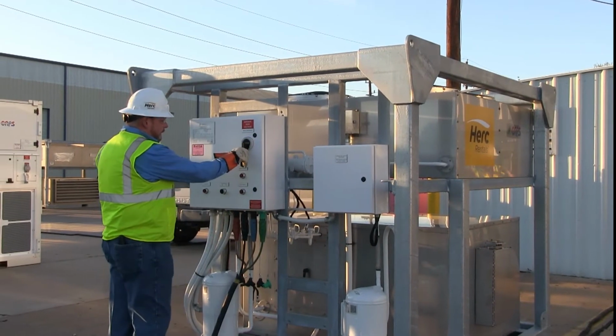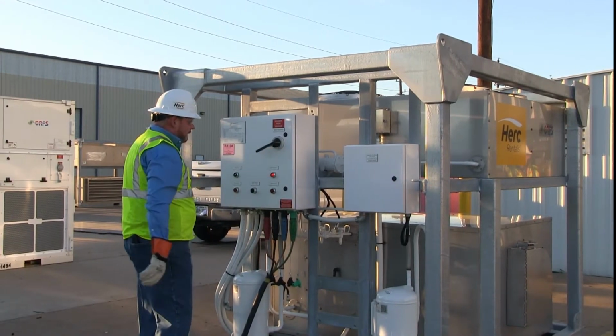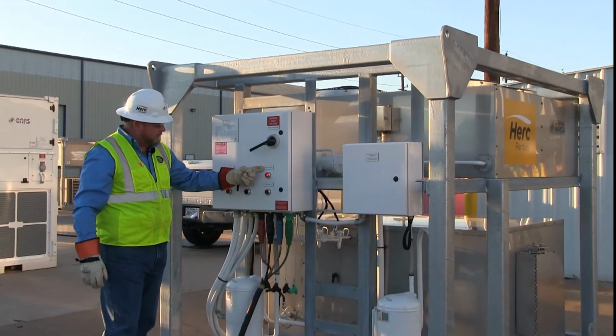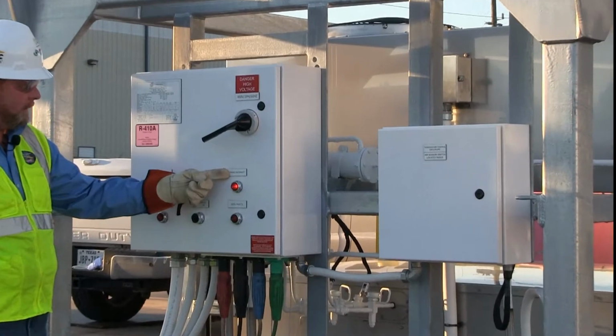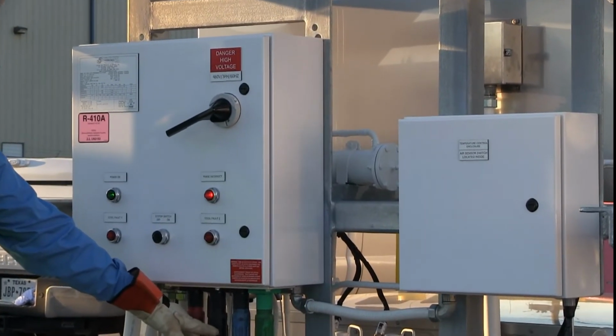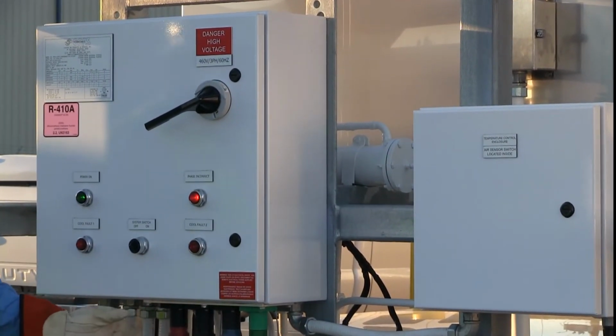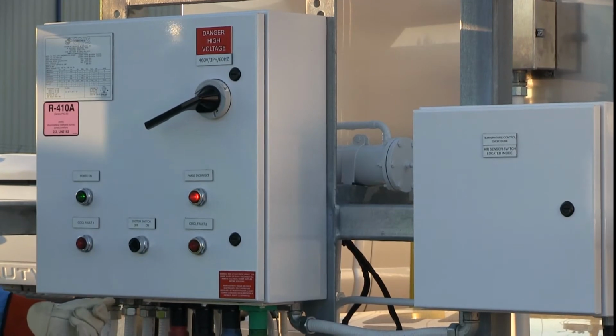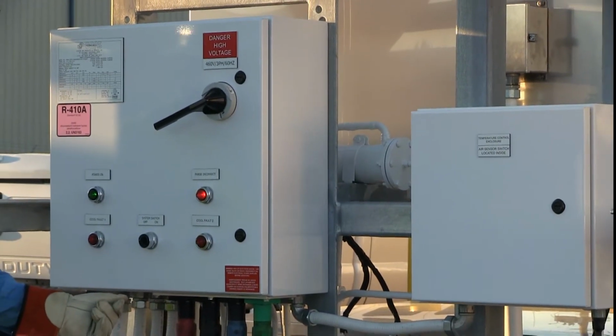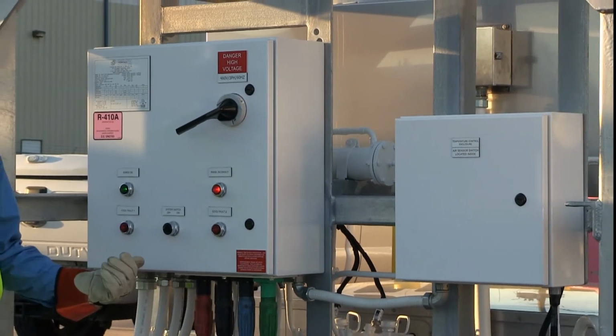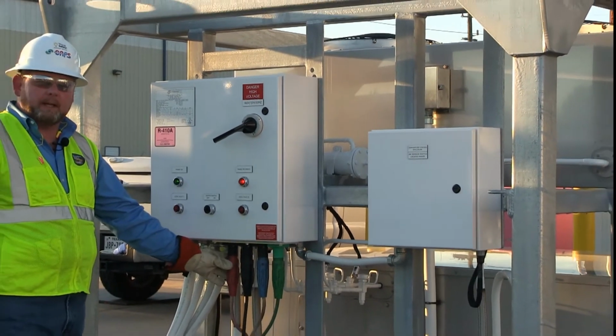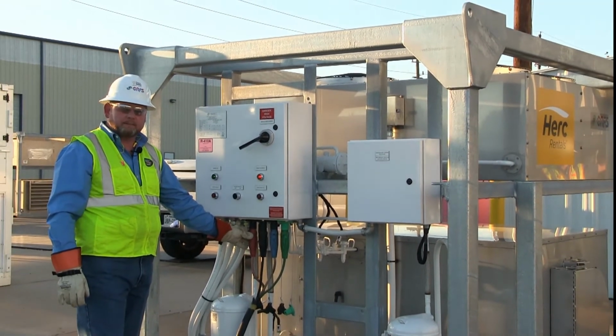We're going to go to the main circuit breaker, turn it on. The first thing we discover is the phase incorrect light is on, which indicates that two of our phases are backwards. We'll have to correct this by turning the power off, locking and tagging the machine now, and reversing two phases. Please note, you never change the cam locks while they're energized.